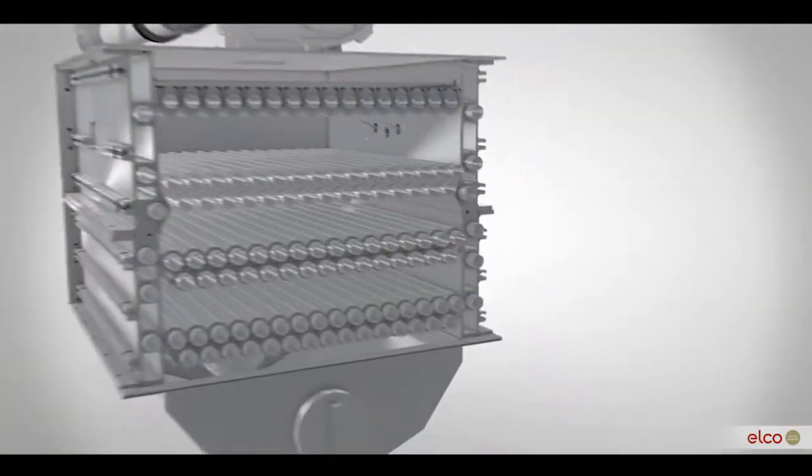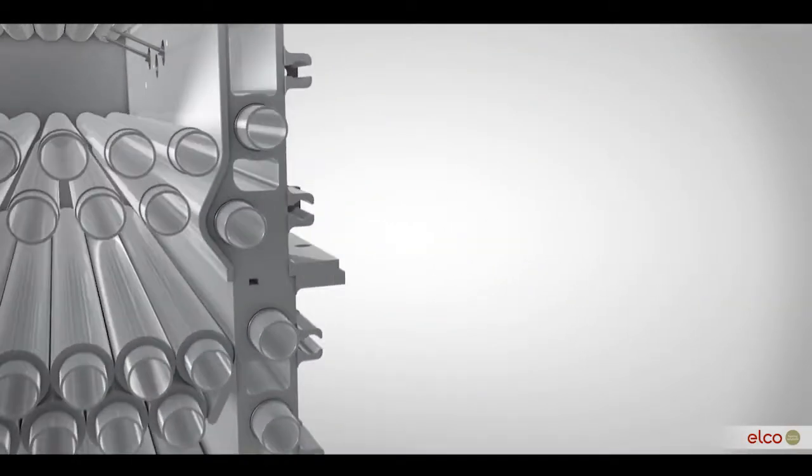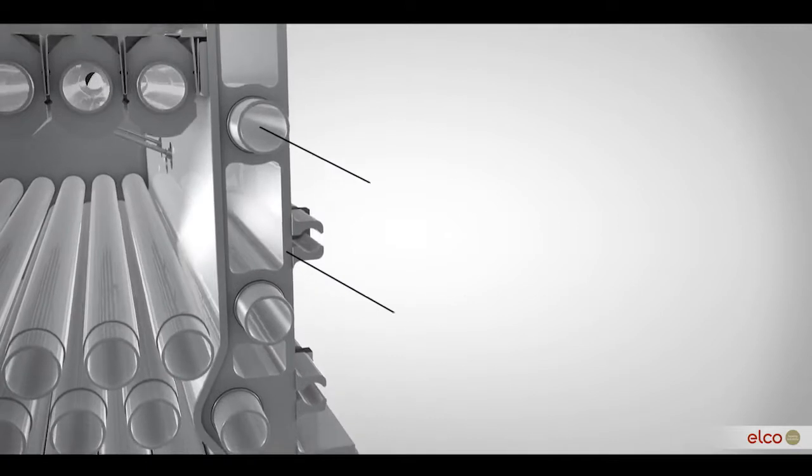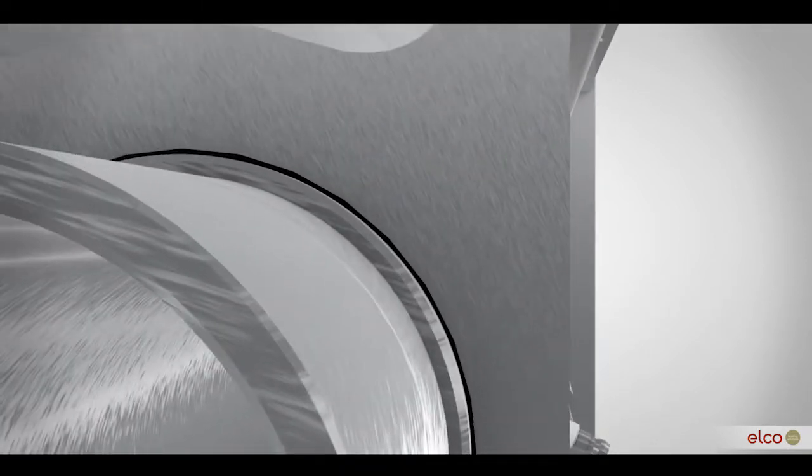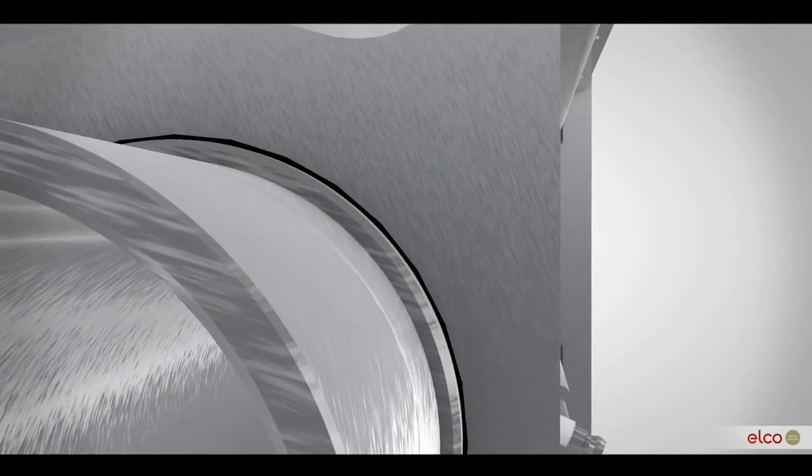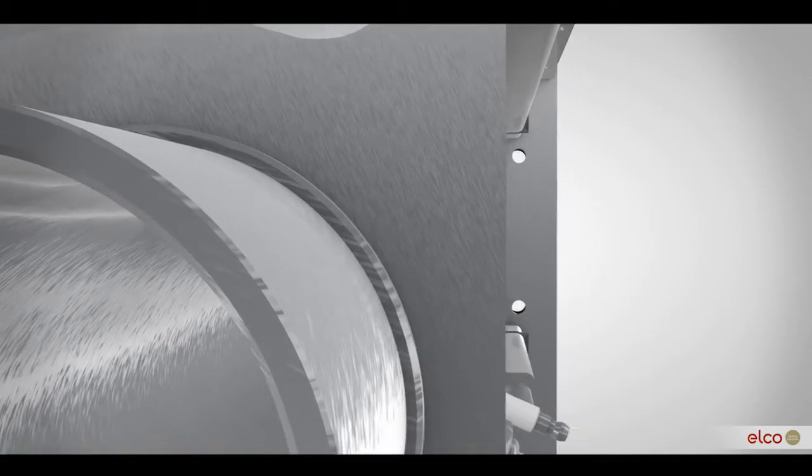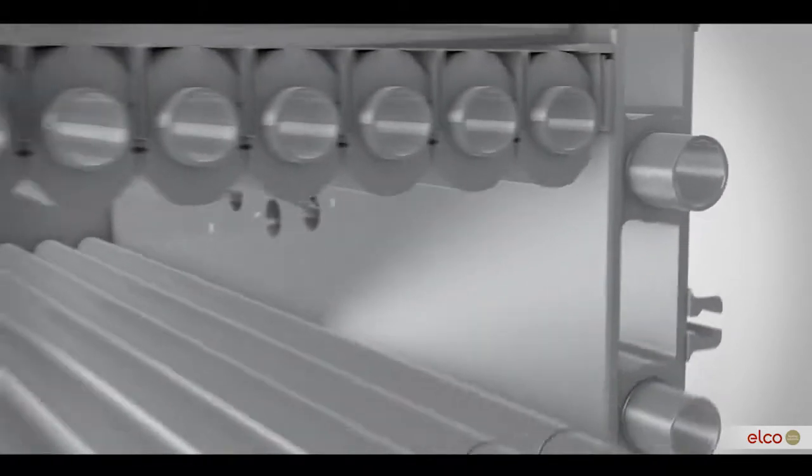To prevent heat loss, the side walls of the heat exchanger body are water cooled. Heating system water is led through stainless steel tubes which are integrated in the outer wall of the heat exchanger. The use of hydroforming technology ensures optimum contact and heat transfer at all times during the entire lifetime of the boiler.